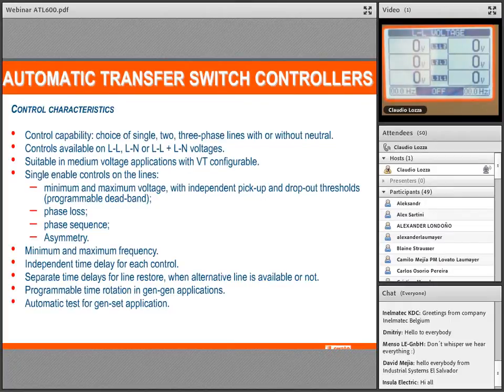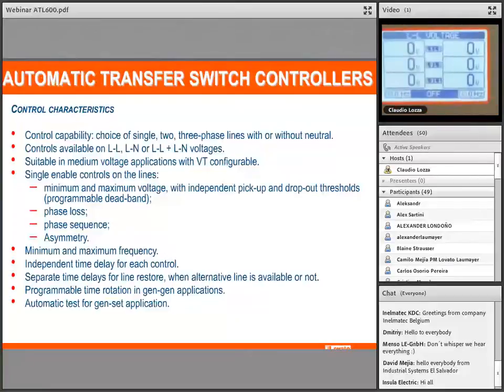Then the thresholds, the control that I can set up is, for example, in a minimum maximum voltage with independent value and independent time delay. So I can select the dead band. Then we have the control in phase, for example, phase loss or phase sequence, and the asymmetry. Then the control for the frequency. And as I said before, all the parameters can be managed with independent value and time delay.